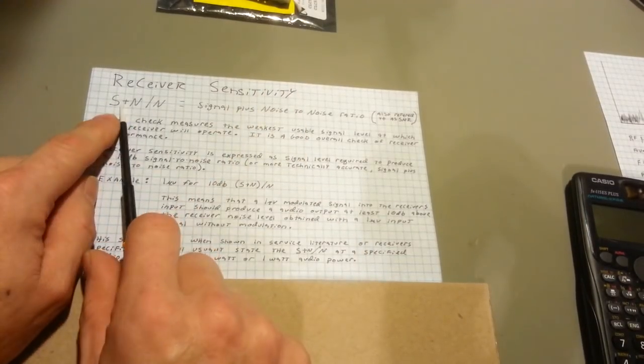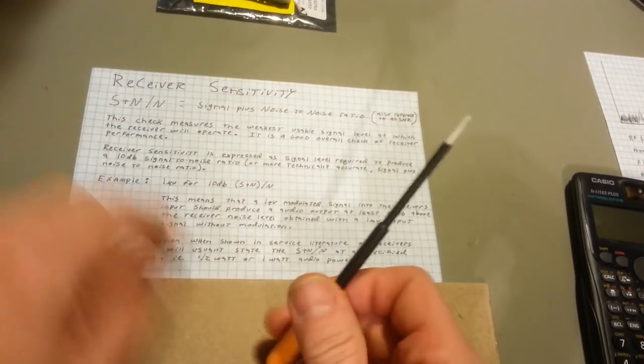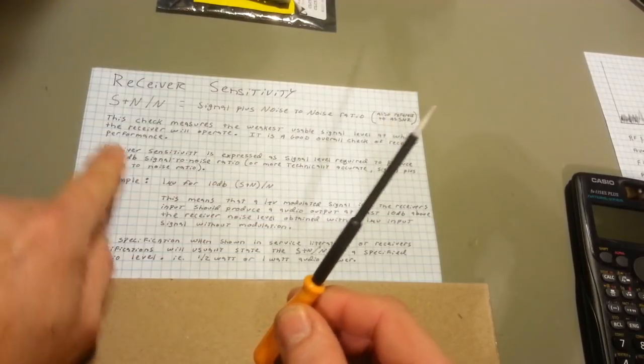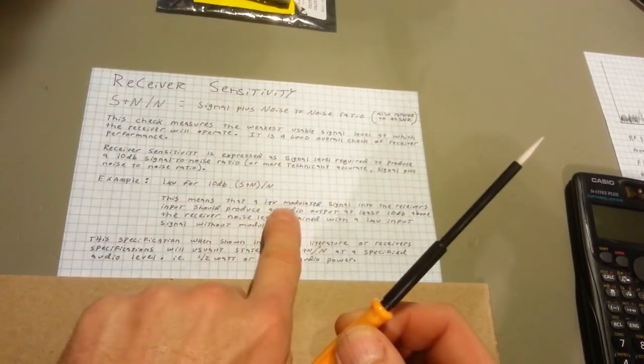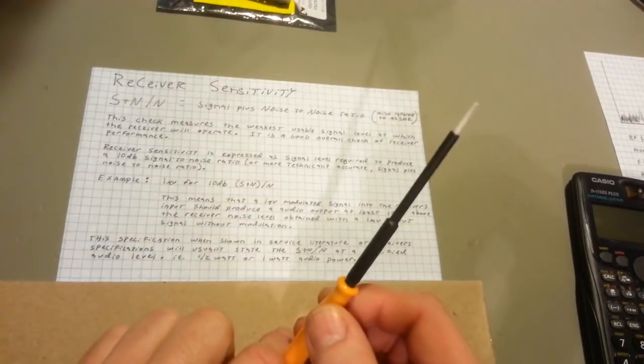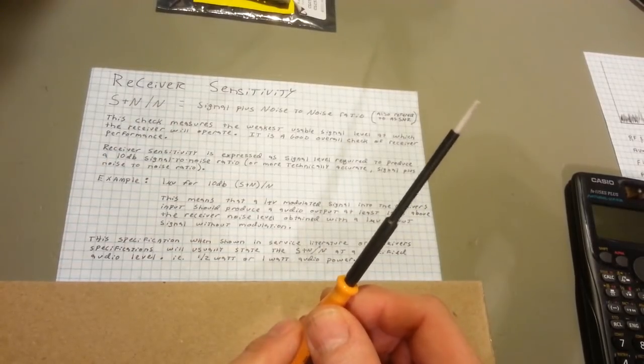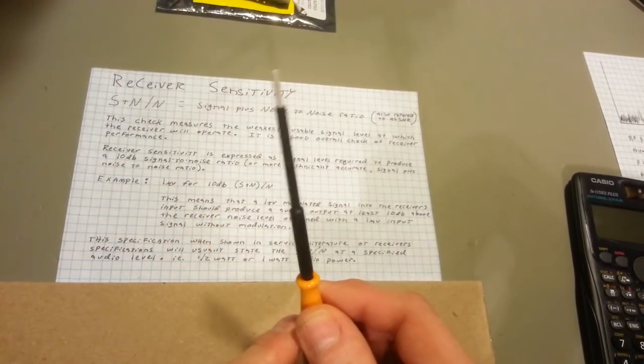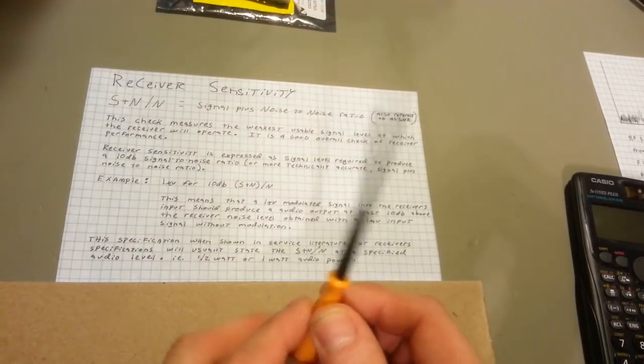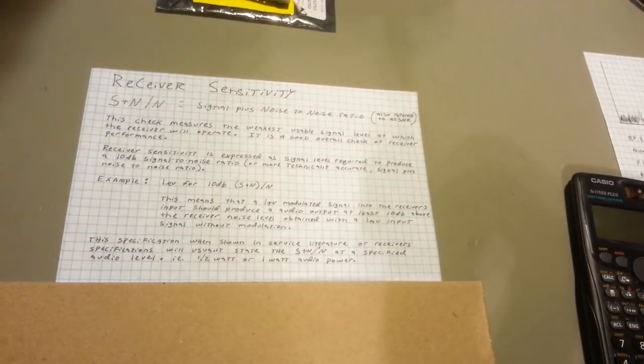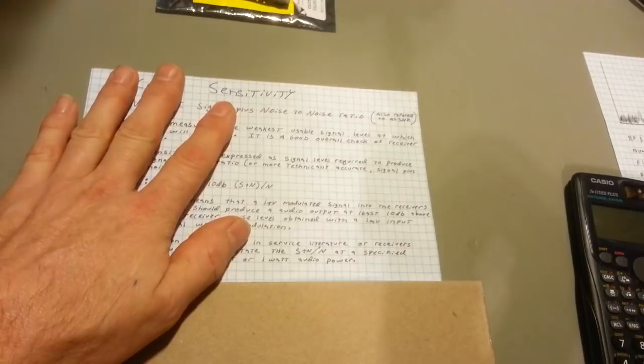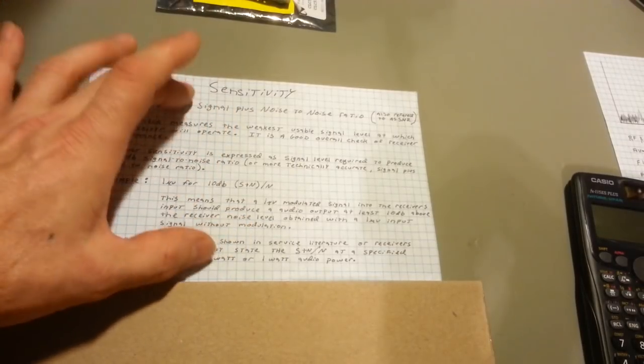Or if you took your signal plus noise measurement first, and you set your needle to 0 while injecting the modulated signal, and then you turn off the modulation, it should not decrease more than 10 dB. There's a 10 dB difference between that. That's all that is. And like I say, it's been around for years, and manufacturers still use this specification.